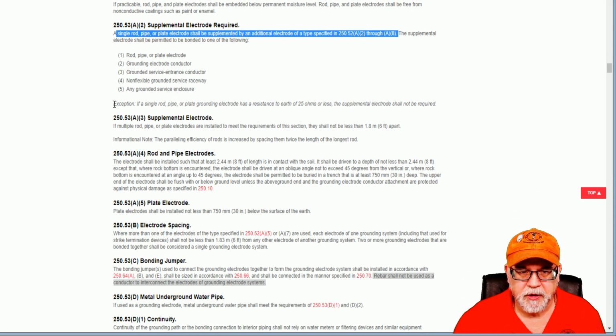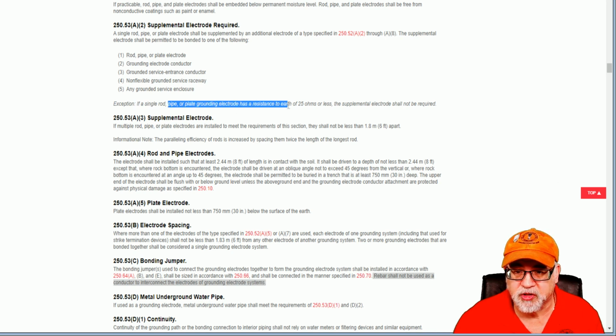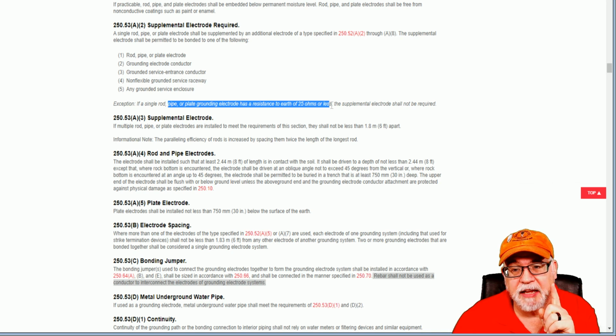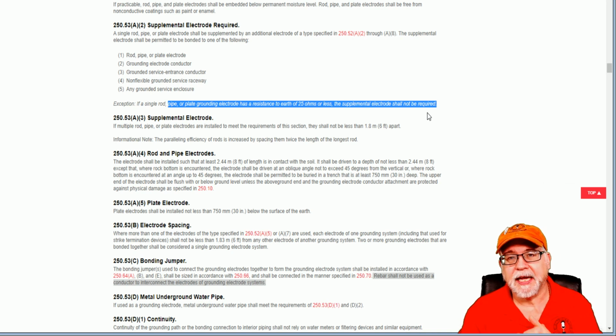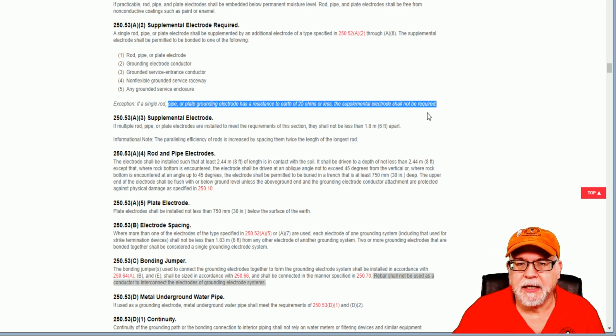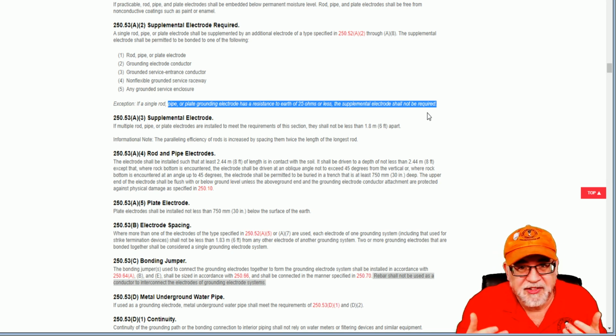Now, what's the exception? The exception says if a single rod, pipe, or plate ground electrode has a resistance to earth of 25 ohms or less, which answers our question, the supplemental electrode shall not be required. Okay? So, anytime you're putting in a grounding electrode system that is going to be a rod, pipe, or plate, it's required to be supplemented unless you can apply the exception. And it's on you to be able to show the electrical inspector that it's 25 ohms resistance to earth or less. And you're not going to do that with a standard meter. You're not going to do that with a standard ohms meter.